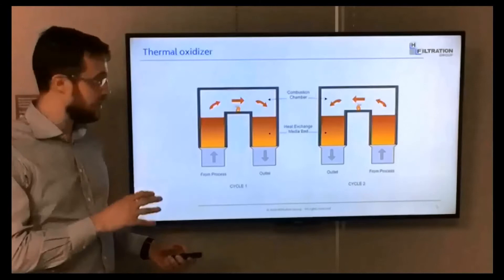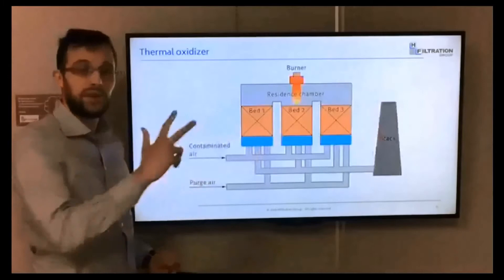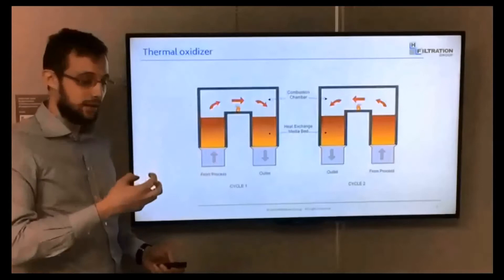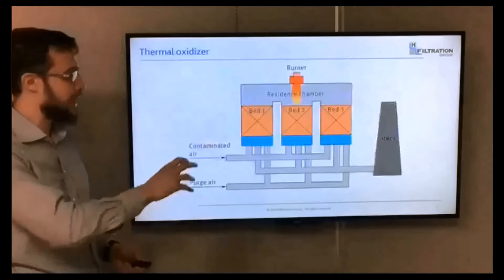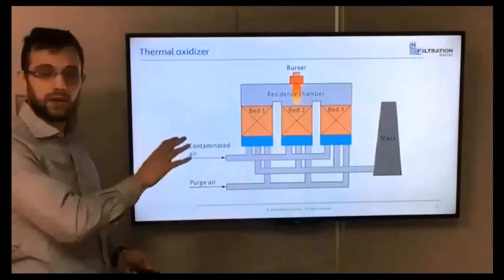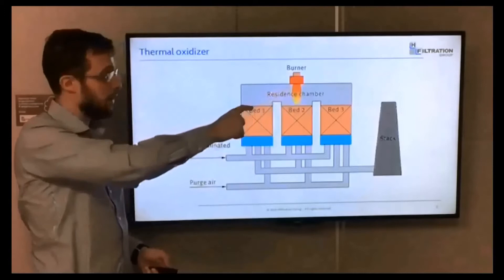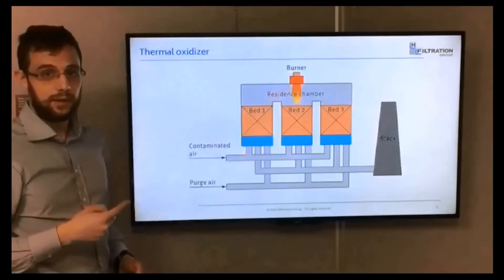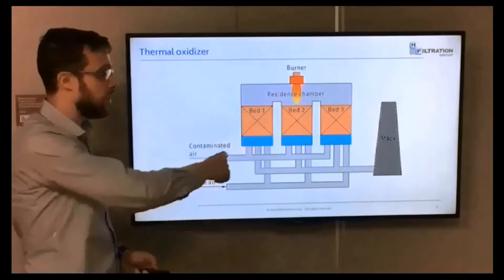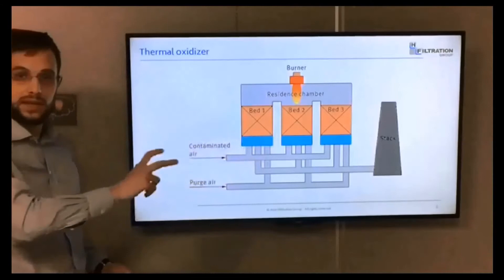This is a two-bed configuration, and this is a three-bed configuration — the concept is exactly the same. In the two-bed configuration, during the valve switching, some VOC can remain captured in the ceramic bed. The three-bed configuration with proper valve switching timing avoids this issue. In the three-chamber configuration, some air is also used to purge and clean the bed during switching.